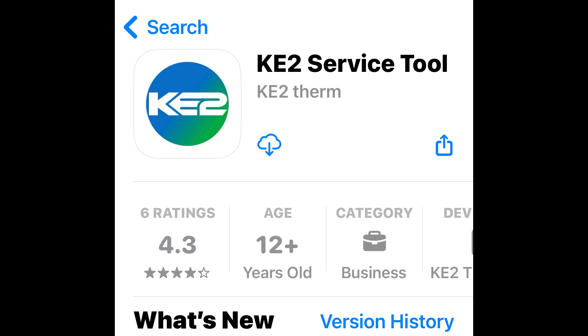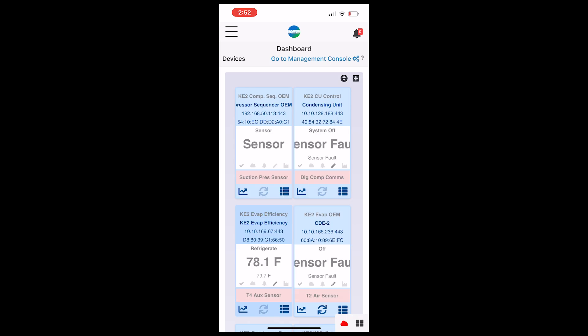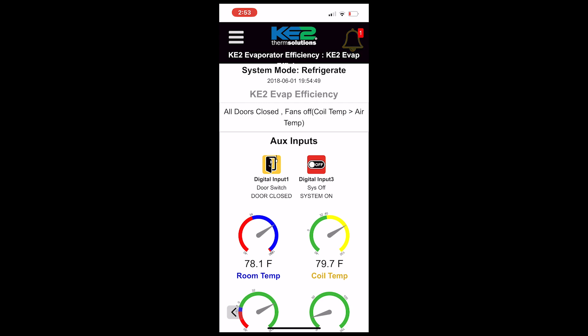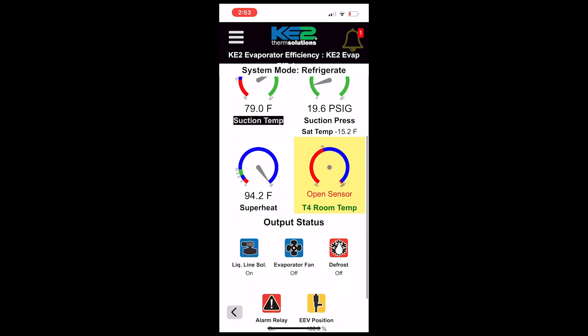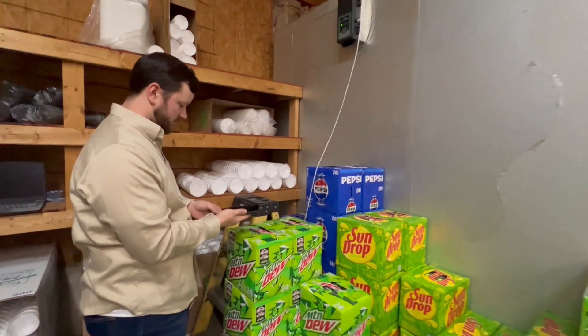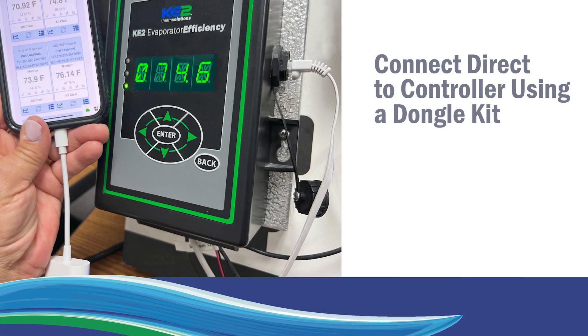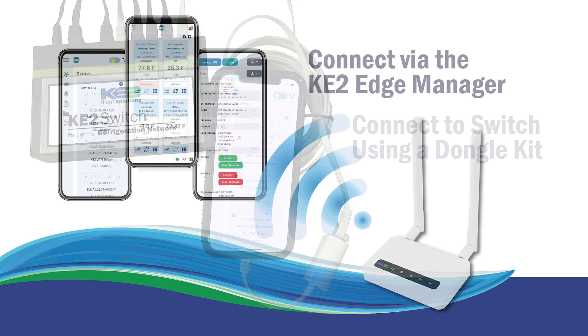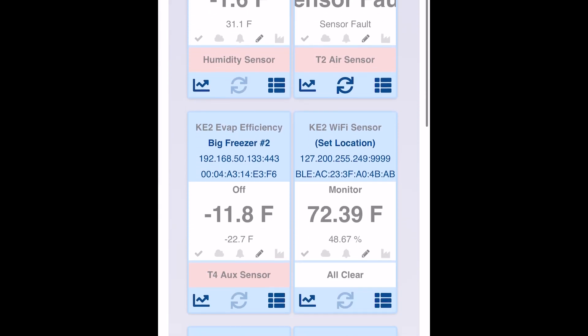The KE2 Service Tool is an app developed for your smartphone or tablet that allows you to easily access KE2 Therm controller web pages. You can greatly improve the efficiency of your service calls by seeing everything from temperature and pressure to valve position and relay status, all without hooking up gauges and in many cases it requires no time in the refrigerated space. The app connects to your controllers either directly to an individual controller with the KE2 dongle kit, to a switch using the dongle kit, or if you're using a KE2 Edge Manager router you can wirelessly connect and see all the controllers on that network.